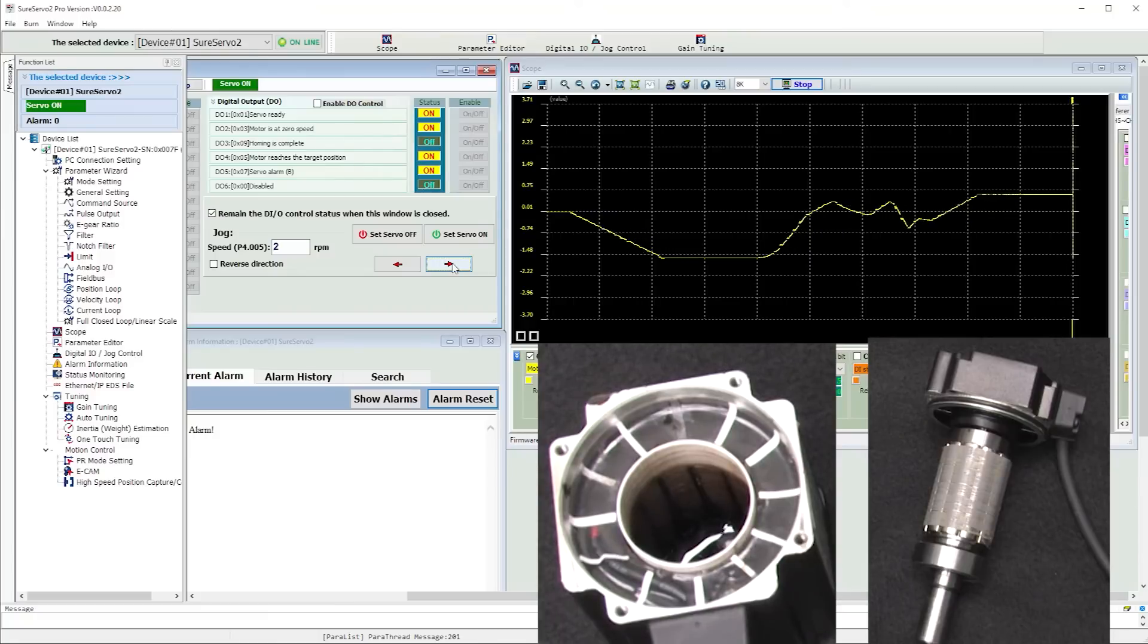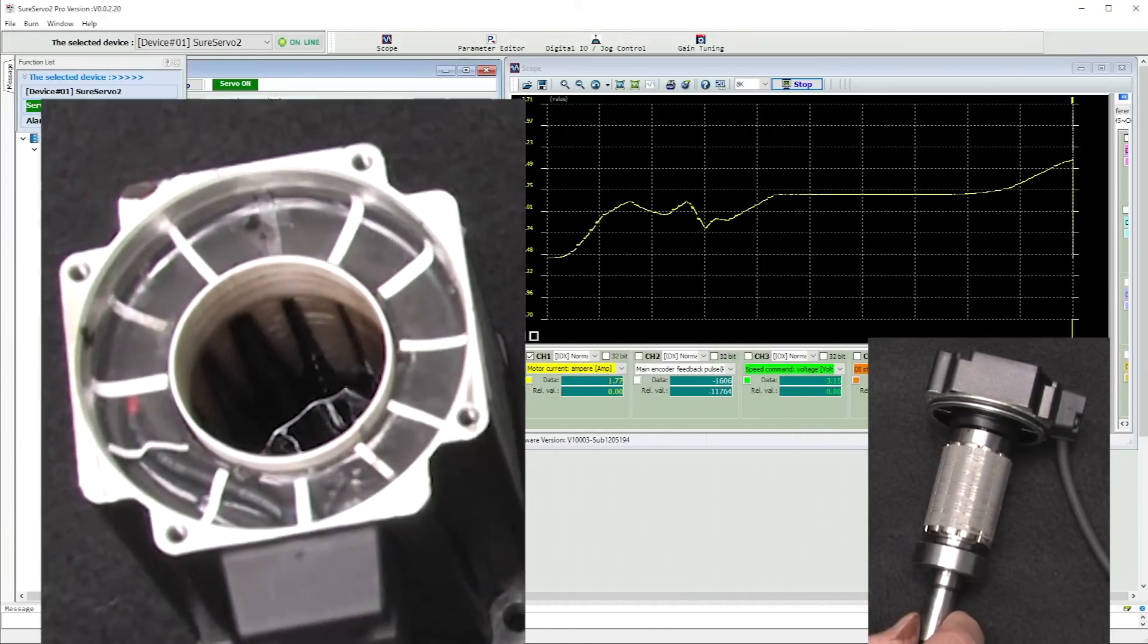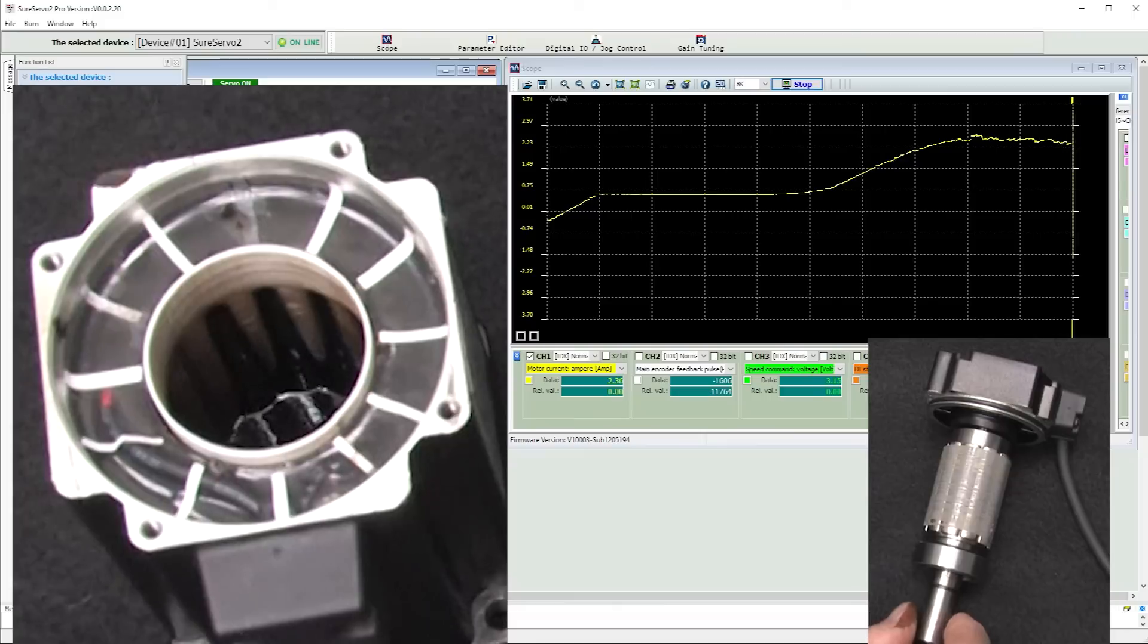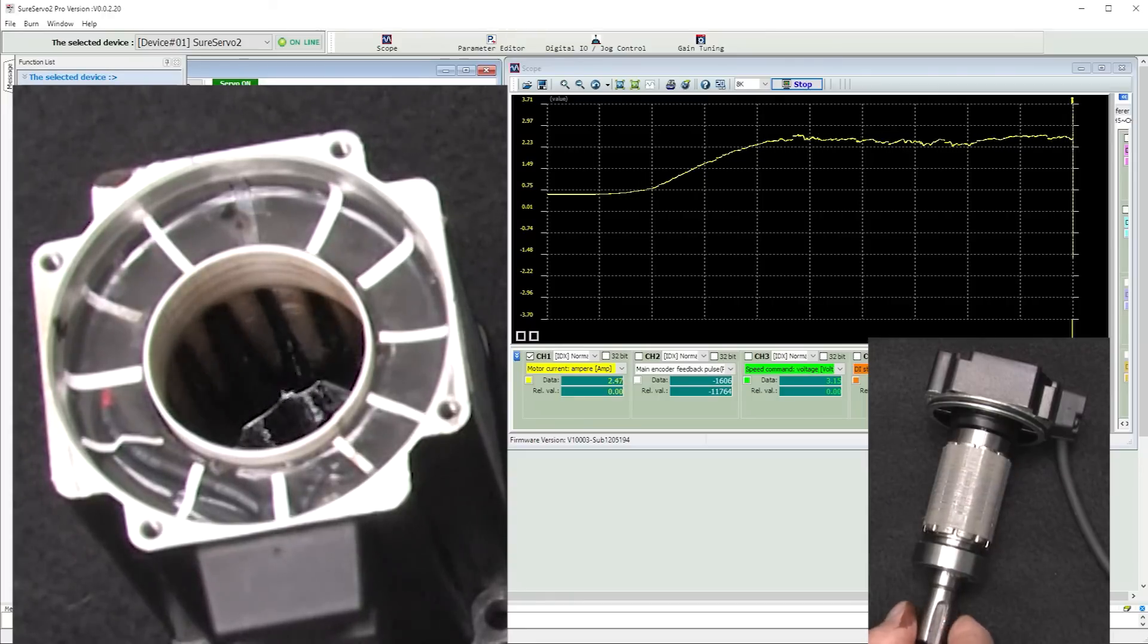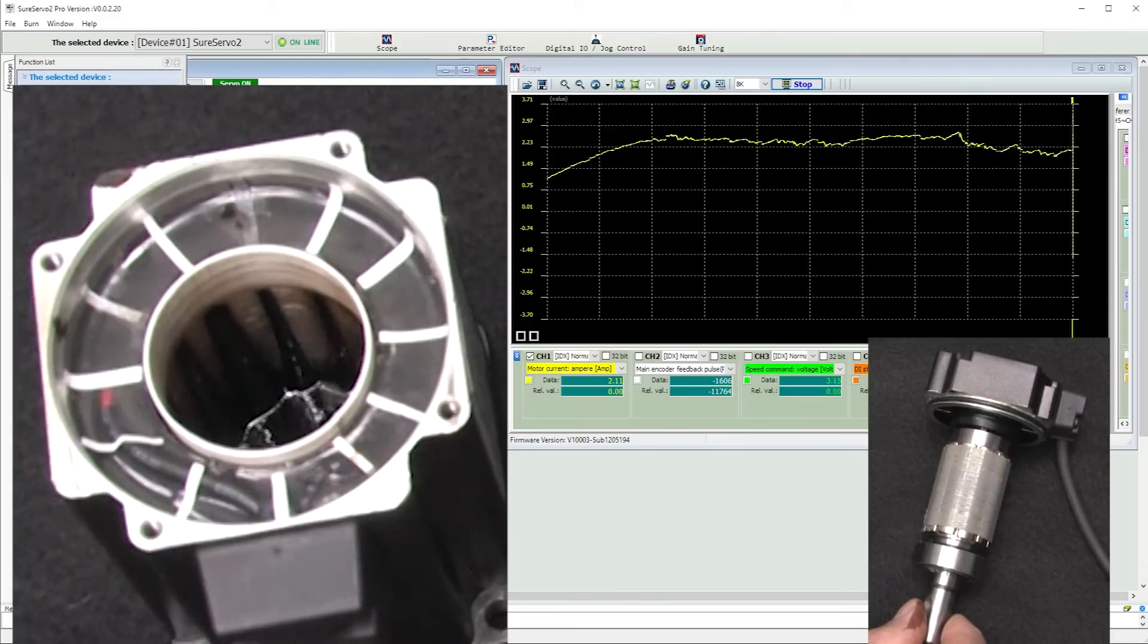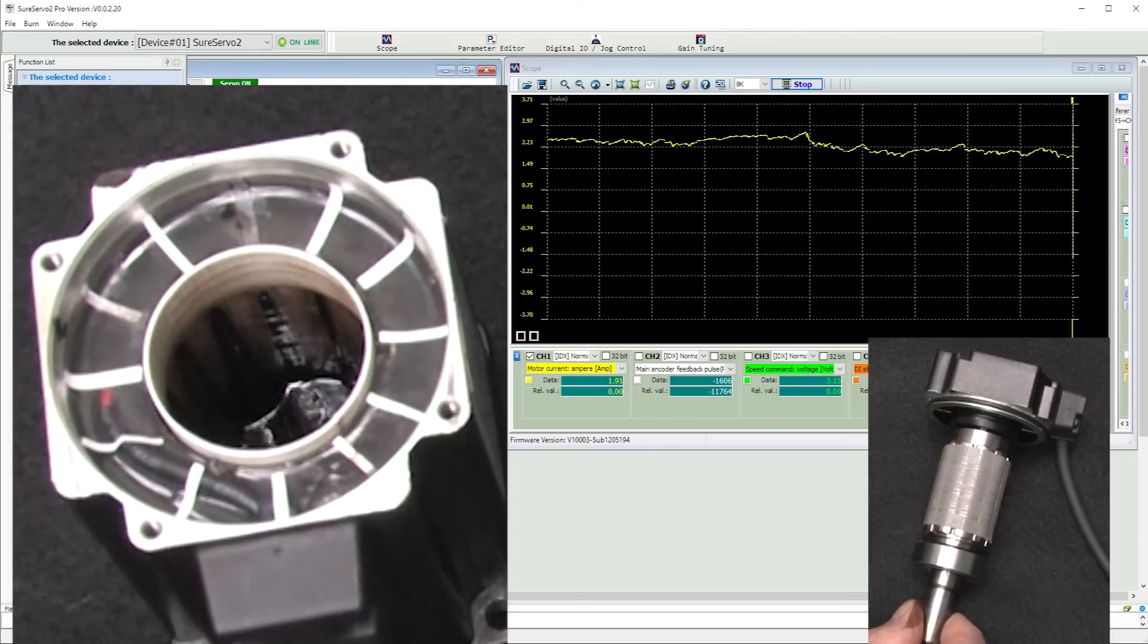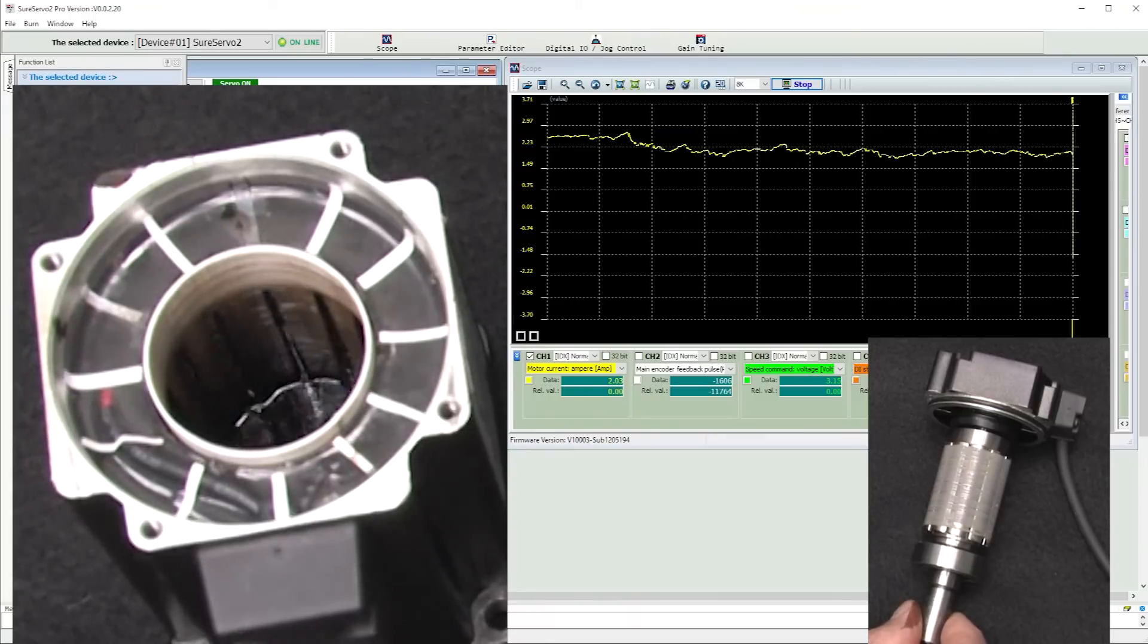OK, now I'm going to attempt to hold the jog button down and rotate the rotor at the same time to simulate what the drive would normally be doing. As I do that, you can actually see the stator magnetic fields rotating around. How cool is that? And that's the beauty of the three phase AC input to the stator. The drive can smoothly move the rotor to any position simply by adjusting the currents at each of the three phases to create whatever magnetic flux it needs here on the stator to move the rotor wherever it wants. We call that synchronous because the rotor is always going to follow the stator's magnetic flux exactly, unlike the asynchronous AC induction motors where the rotor always lags the stator flux.